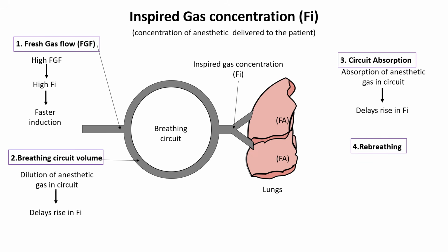Rebreathing occurs when exhaled gases containing carbon dioxide and some anesthetic agent are returned to the patient. Exhaled gases, which contain lower anesthetic concentrations after uptake by the alveoli, mix with the fresh gas, reducing the inspired concentration unless compensated by a high fresh gas flow.